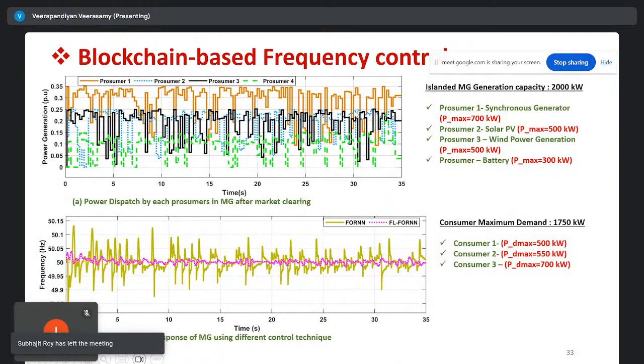The dispatch command for each generator or prosumer is given for the case of frequency regulation. The frequency of the system is tightly regulated by the FL-FORNN compared to the FORNN control, and both are within the band. The frequency regulation standard says the frequency should be maintained within plus or minus 0.2 hertz. The results show the frequency maintained between 49.8 and 50.2, which is within the standard limit. The right side shows the power capacity each prosumer is participating with in the peer-to-peer energy trading, and the total microgrid generation is 2000, which is 2 megawatts.